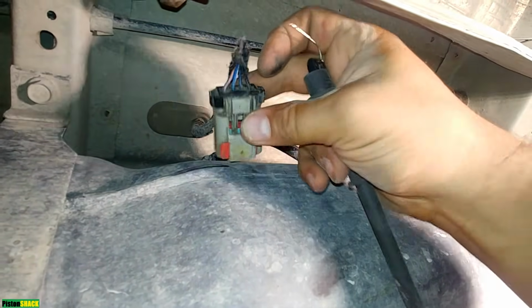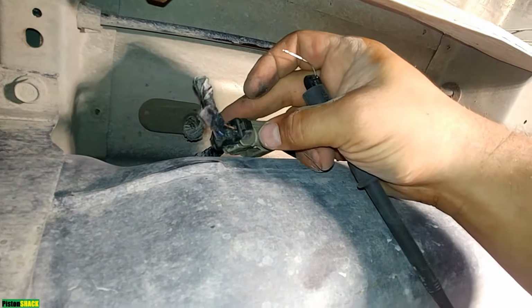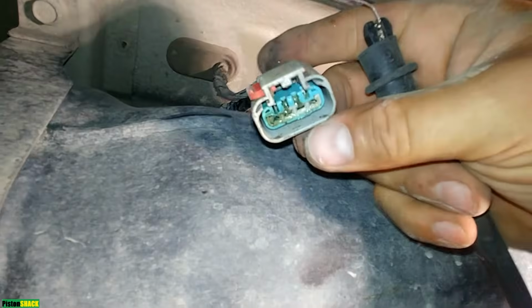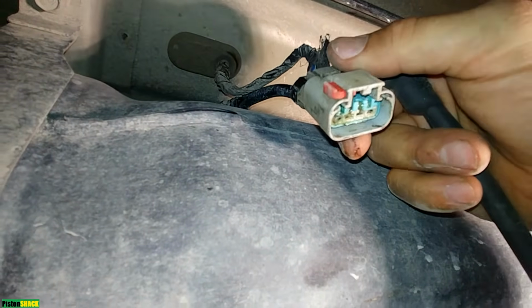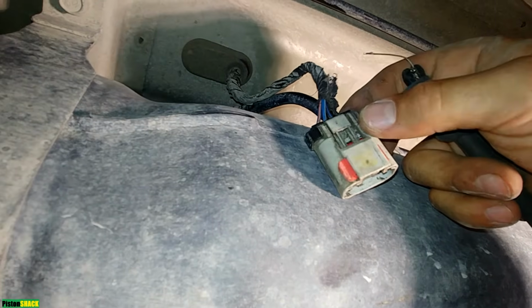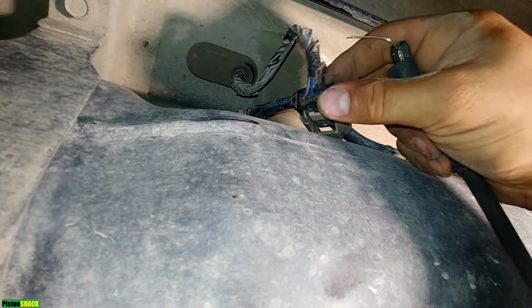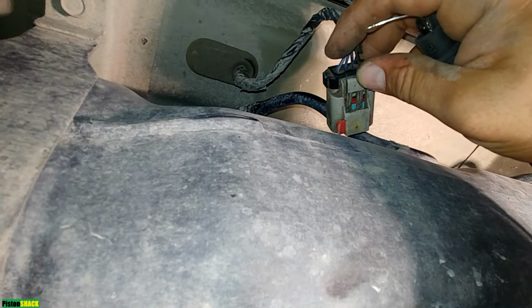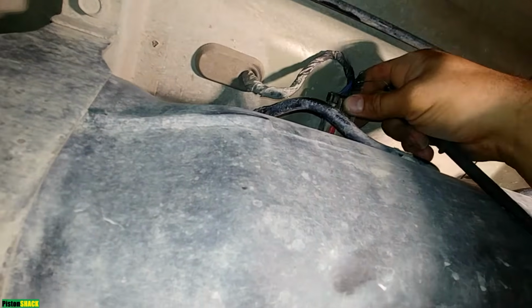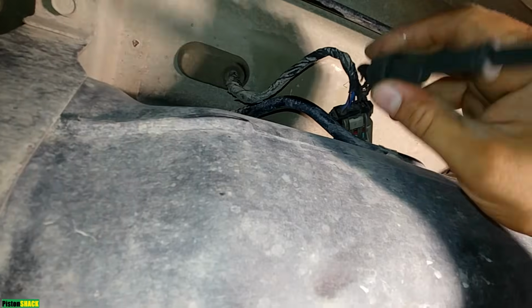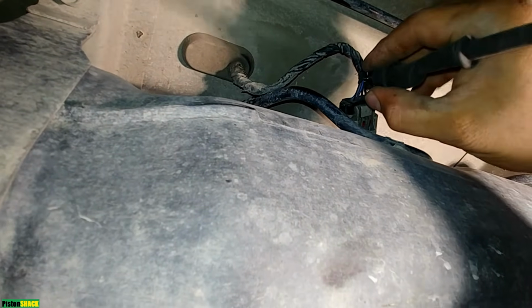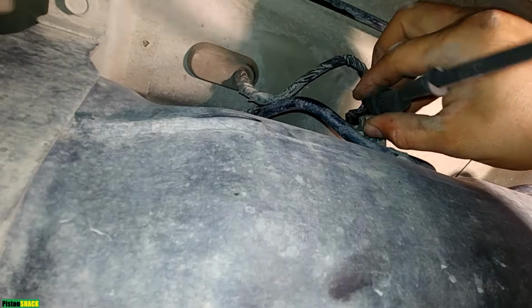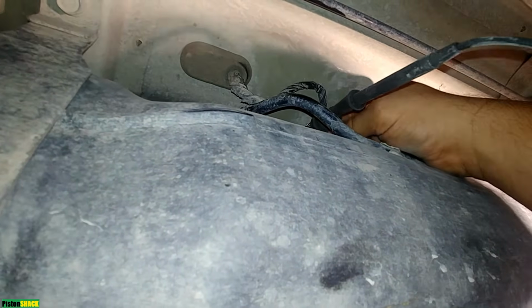Okay, an idea is to test it under load, because what a multimeter does is only show the potential between 2 points, and to know the exact condition of the circuit, we have to put a load, at least turn the key to the on position and see. And we're going to back probe here and check for power and a ground. Let's just put a tip in here where our power is, and put it back.